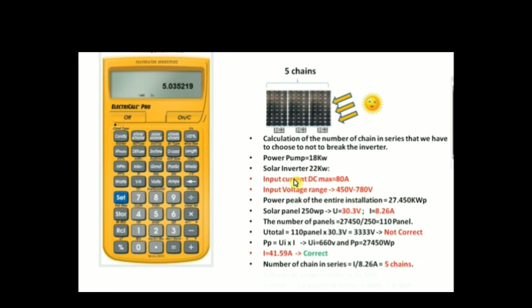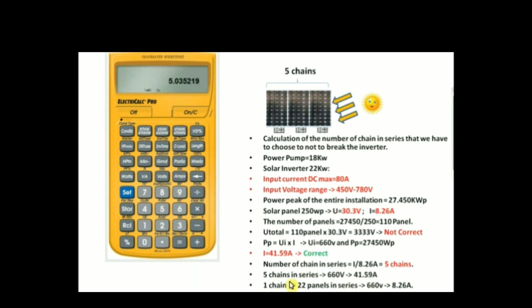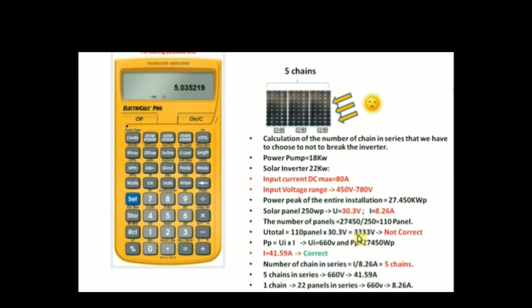In the end, we have five chains in series delivering 660 volts and 41.59 amps in total. Each chain contains 22 panels in series and delivers 660 volts and 8.26 amps. This is how we feed our pump without breaking the inverter. Thank you for your attention and see you in the next tutorial.